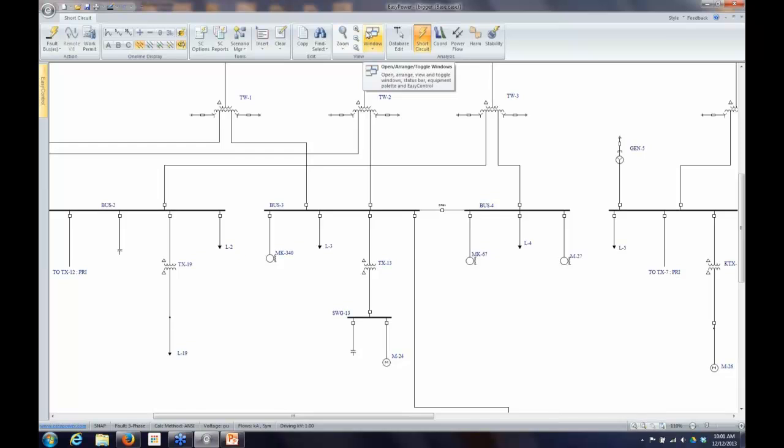If I had any missing information in my model that would prevent EasyPower from doing the short circuit calculations, I would get an error message at that point, and it would provide me with a list of missing information or problems with the model. Things like cable lengths, impedances, motor horsepower, X over R ratios — those will prevent you from getting into short circuit at all.